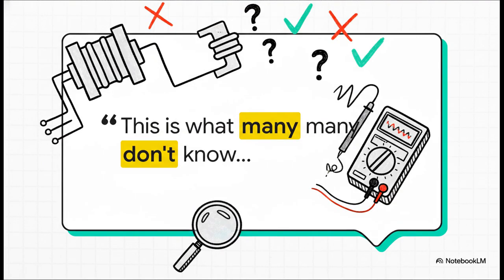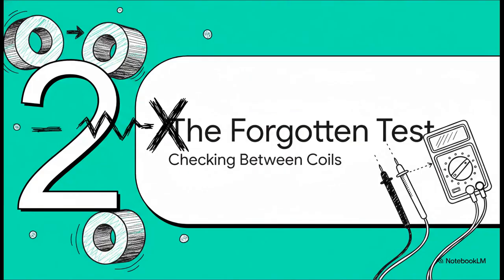And this is a really crucial point. This is the kind of thing that even some experienced techs can miss, but it's the one thing that separates a good diagnosis from a bad one. This next test is what truly tells you if your transformer is healthy. Okay, here it is, the test that almost everyone forgets to do. You absolutely have to check for a connection between the primary and the secondary coils. See, this isn't about testing the coils themselves, it's about making sure they are isolated from each other.